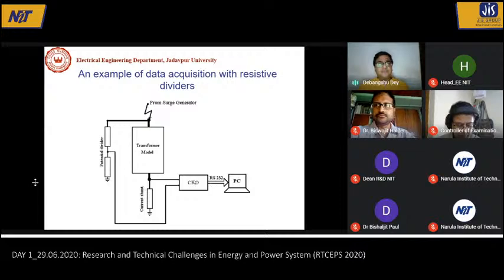For example, if we are trying to assess transformer condition in terms of impulse response, it is a typical test for the transformer - not a routine test, but a type test. Whenever the manufacturer demands that the transformer should have enough capability or insulation to withstand the impulse waveform, we have to perform this type of test.